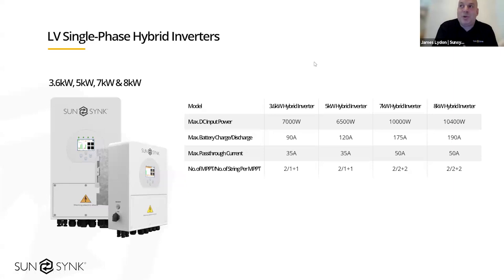The 7 kilowatt's great as well because most DNOs are doing the G99 fast track, and that's on any systems up to 32 amps. So our 7 kilowatt hybrid inverter fits well within that gap. On the 7 kilowatt, we've got a 10 kilowatt MPPT. With the 7, there are 2 MPPTs and 2 strings into each MPPT, and it's the same with the 8. So there are 2 MPPTs and 2 strings into each MPPT, so 4 strings in total. And then the 3.6 and the 5, we have 2 MPPTs with 1 string into each.